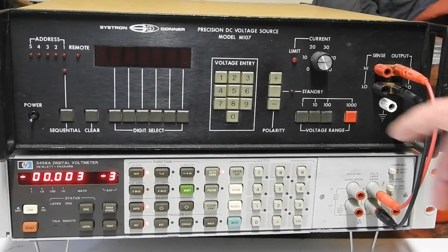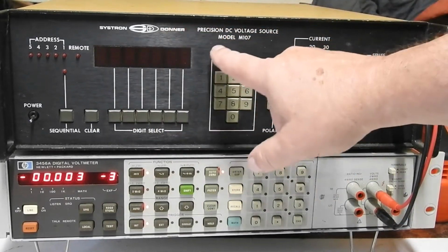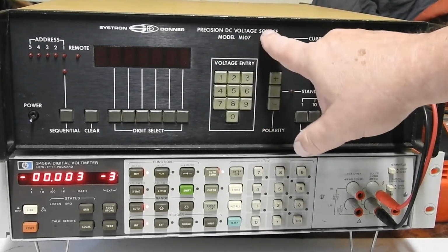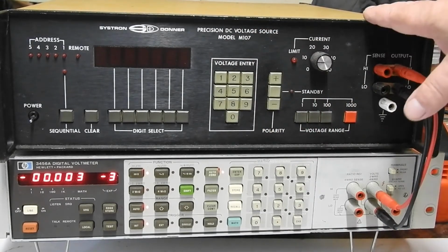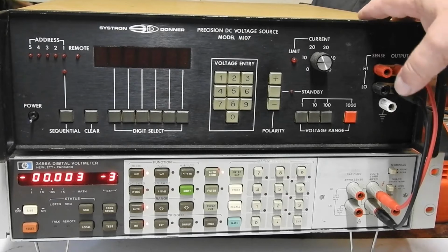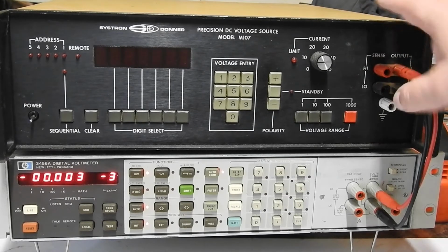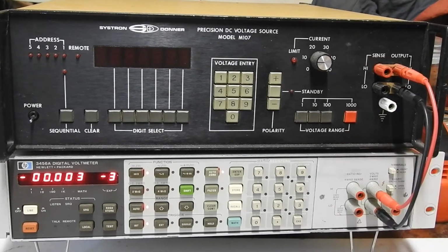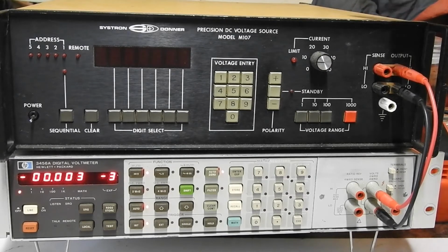At the top we have a Systron-Donner model M107 precision DC voltage source. I got it a few years ago. It wasn't working and I did some repair and it worked except for the 1000 volt range, but that only lasted a few days before it screwed up again. So I want to see if the same fault that was there before has reappeared, or I know I did some dodgy soldering on one of the boards in there, maybe that's come bad. So we'll have a look.